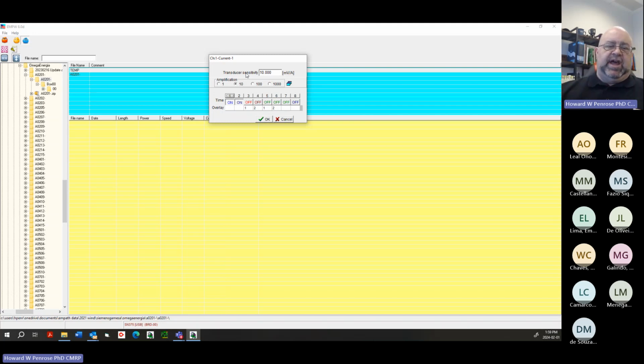One's a 1,000 amp clamp, that's the big one. Chances are you'll be using that most of the time, unless you decide to check yaw motors and so on, just like the generator - then you might use the smaller set of clamps. If you do use the small set, there's a switch on there for 200 amp and 20 amp.